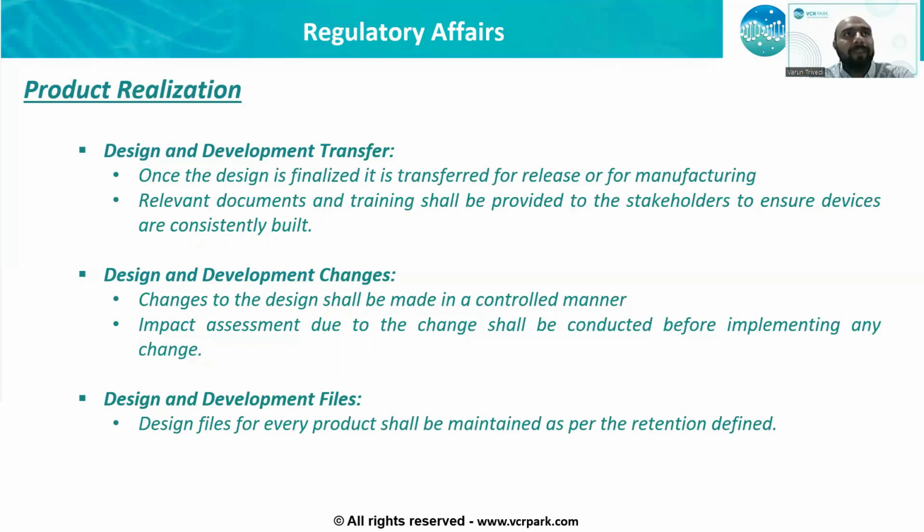Post validation, we do something called design transfer. The design transfer for a hardware device might be as simple as the meeting between the design team and the manufacturing team, where the relevant documents and the training is transferred from the design team to the manufacturing team so that they can go ahead and start bulk production. In terms of software, it might be a stage where once that software development is completed, you basically release the software into the market. Depending again on the type of product, the transfer activity and the process shall be defined accordingly.